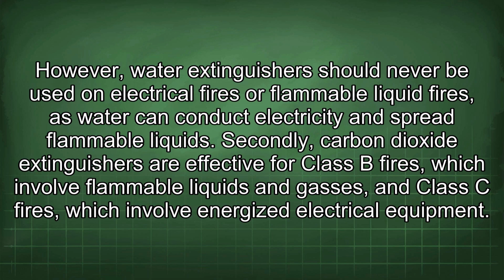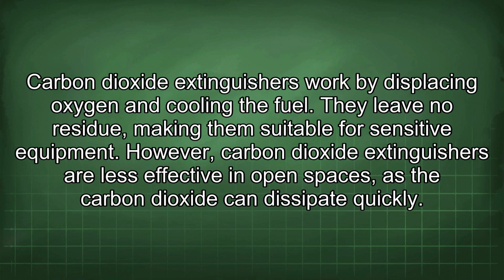Secondly, carbon dioxide extinguishers are effective for Class B fires, which involve flammable liquids and gases, and Class C fires, which involve energized electrical equipment. Carbon dioxide extinguishers work by displacing oxygen and cooling the fuel. They leave no residue, making them suitable for sensitive equipment. However, carbon dioxide extinguishers are less effective in open spaces, as the carbon dioxide can dissipate quickly.